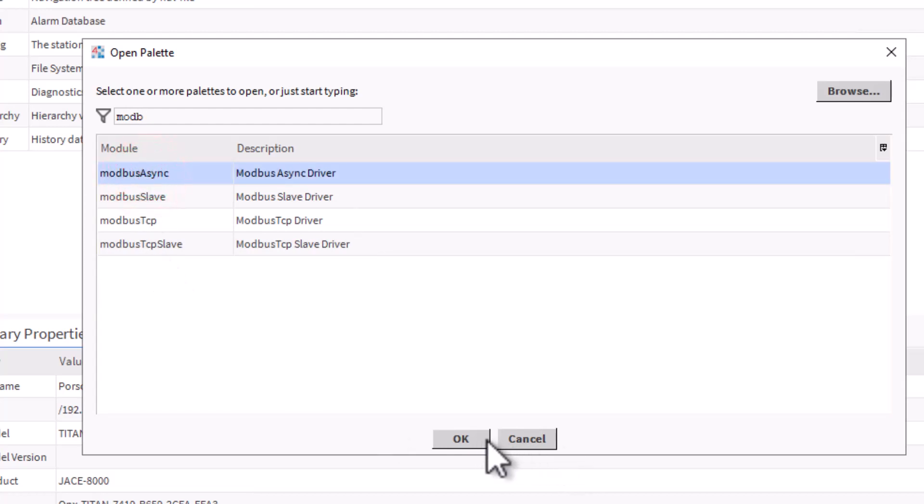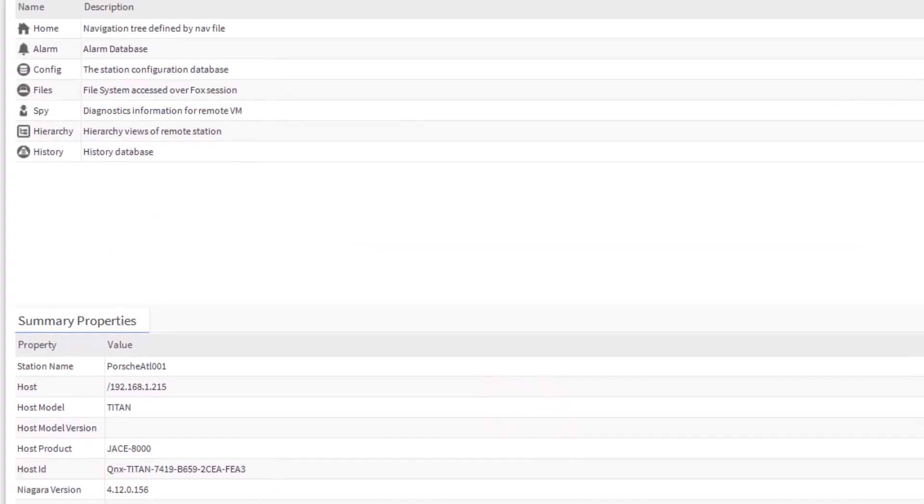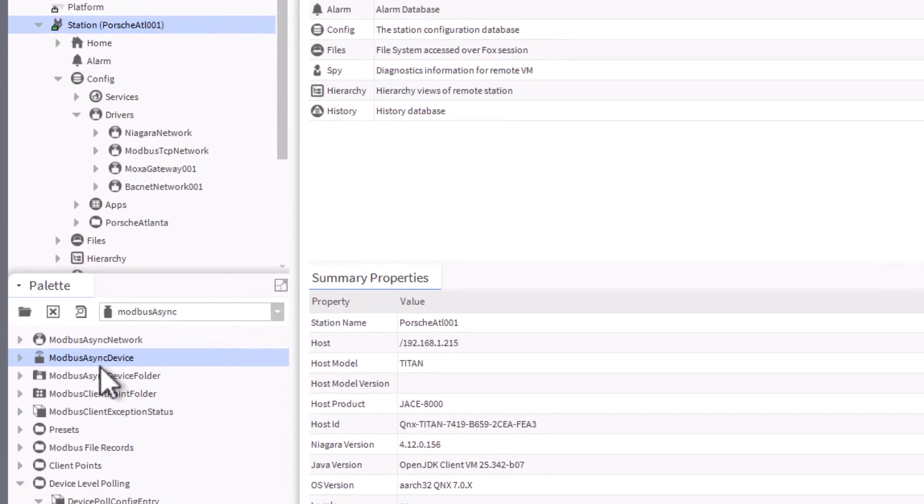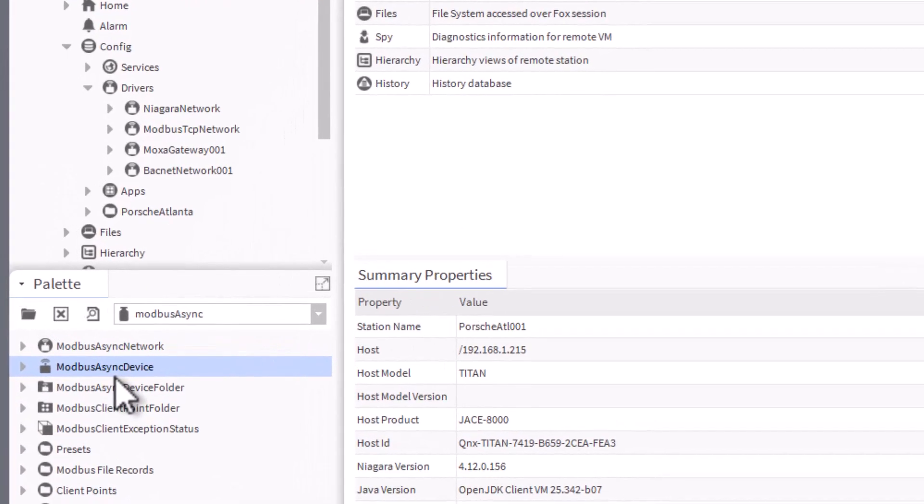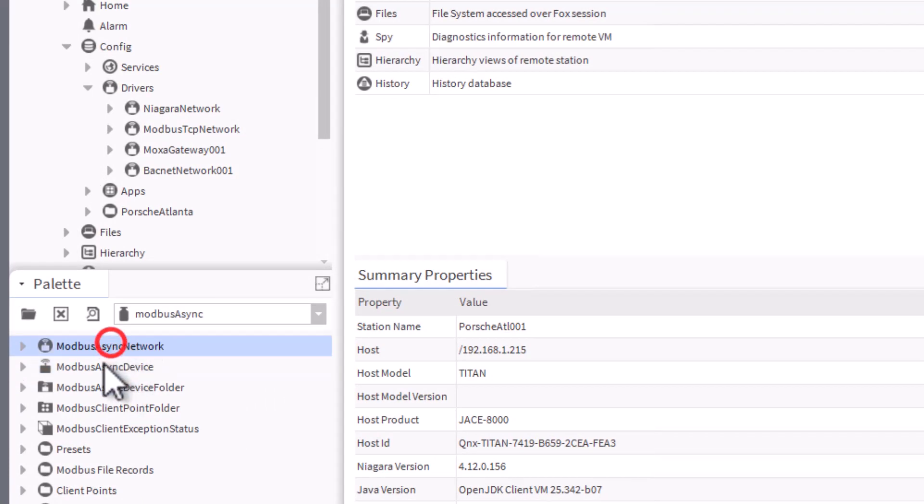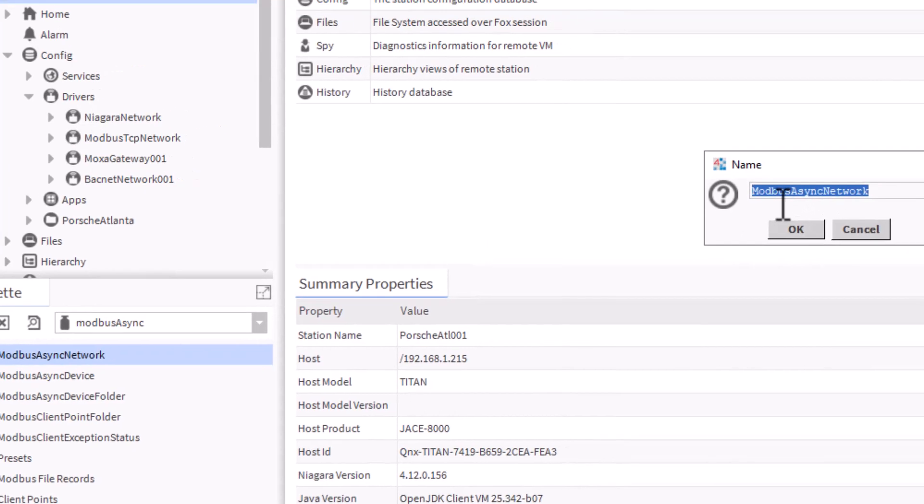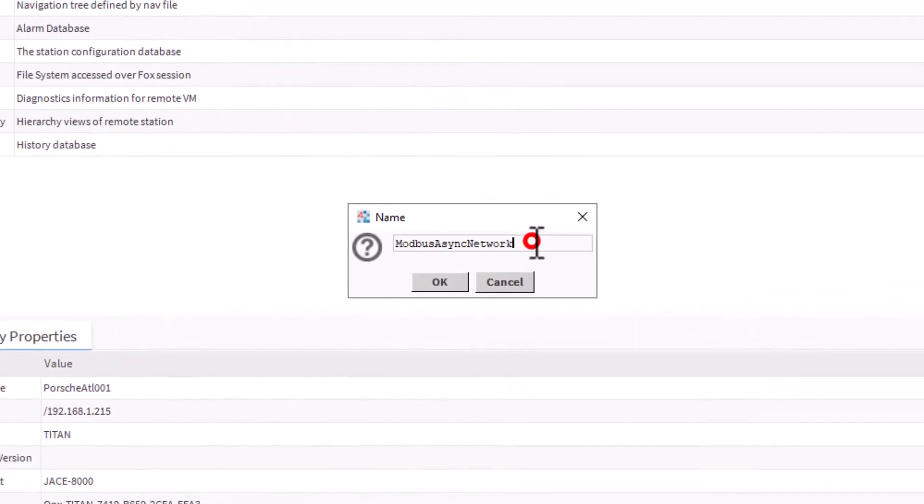Click OK to load that in place. I already have mine, so I'm going to put cancel. First thing we need to do is add that COM port driver that's going to be designated for that COM port. Left click and highlight the Modbus async network, left click and hold, drag it up, hover over drivers, and release. You can see it comes up with our name. Since this is for COM1, I'm just going to put on the end that this is COM1, then click OK.